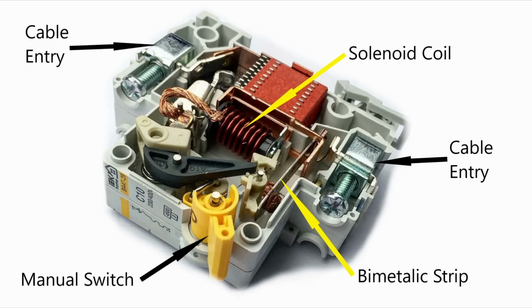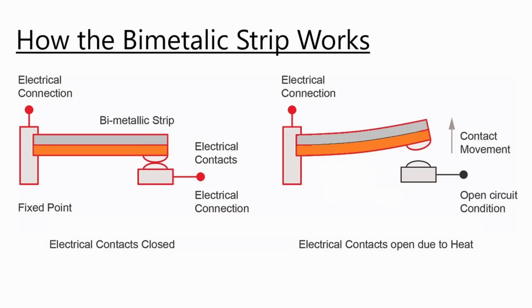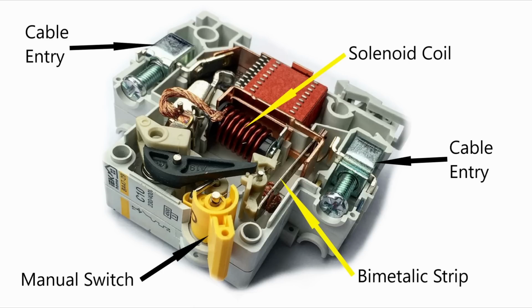Now the bimetallic strip is the key part that makes this device work. A bimetallic strip is made up of two different metals, typically copper or brass and steel, and these metals expand at different rates when they're heated. The electrical current will flow through the bimetallic strip via the contacts. If the current gets too much, the bimetallic strip will start to heat up. The copper or brass side of the strip will expand at a greater rate than the steel side, and because they're physically bonded together, the strip starts to bend. As the heat increases as the current flows more and more through the device, eventually it will bend sufficiently to break the contacts. With a small overcurrent, the heating up of this bimetallic strip may take a few seconds.